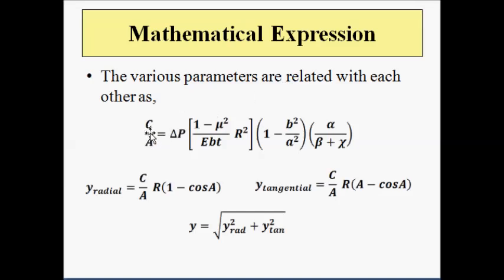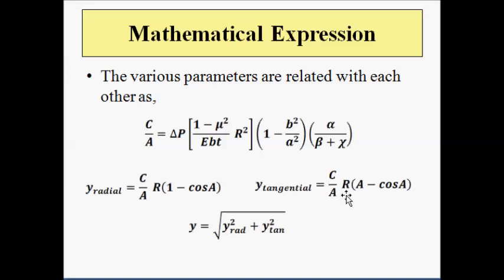The mathematical expression relating pressure difference and coiling angles is: C/A = ΔP × (1 − μ²) / (E × b × t × r²) × (1 − b²/a²) × (α/(β + χ)). The radial displacement of the tube is given by (C/A) × r × (1 − cos A), and the tangential displacement Y-tangential is given by (C/A) × r × (A − cos A). The total displacement is the square root of the sum of the squares of radial and tangential displacements.